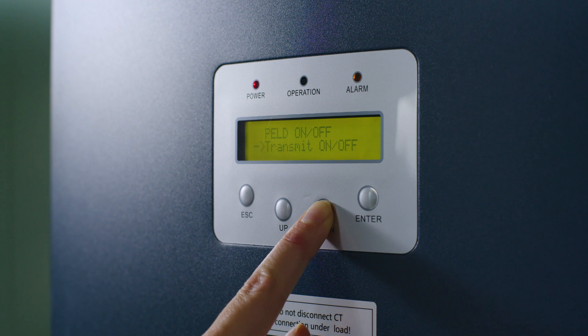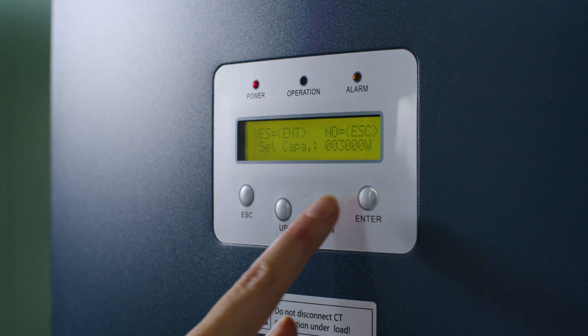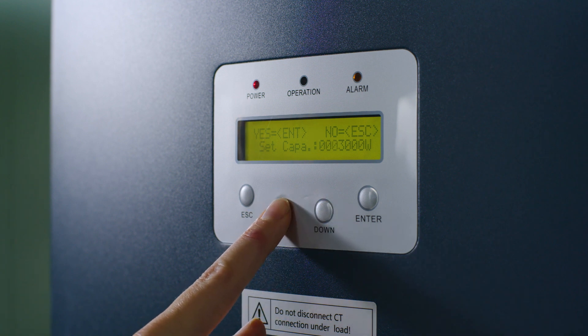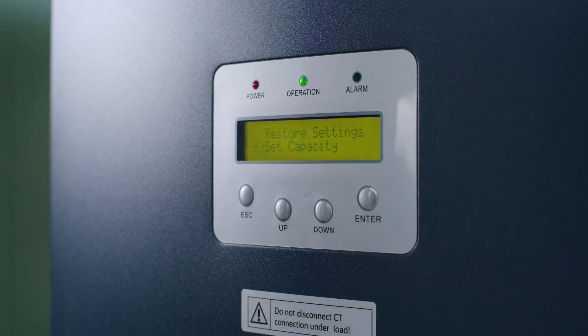Set the total capacity by choosing Set Capacity and clicking Enter. You now see the capacity setting — click Enter. Fill in the total capacity of all inverters connected to the PELD in watts. We have connected one 3,000 watt inverter. Click Enter. The PELD should now show the green operation light. Otherwise, refer to the error codes in the manual.